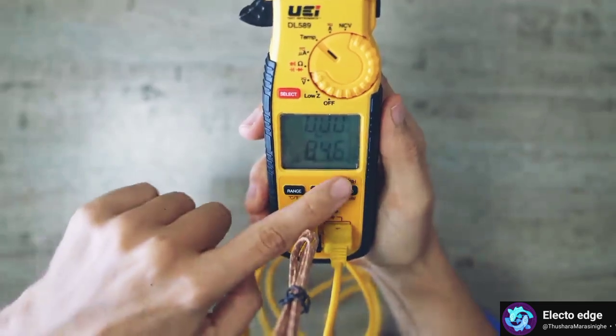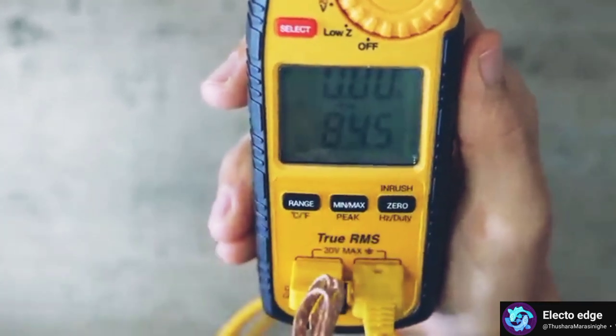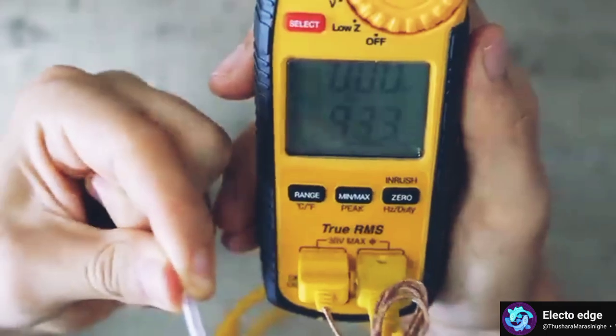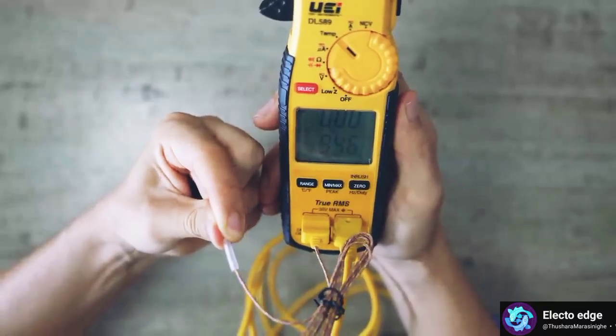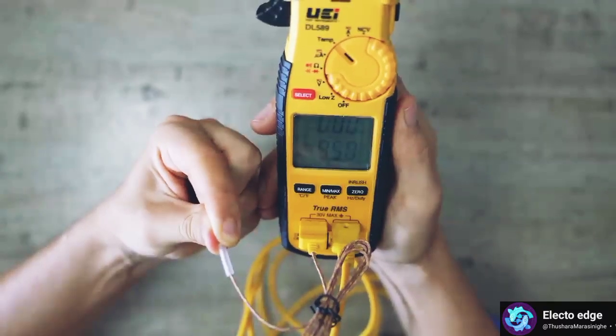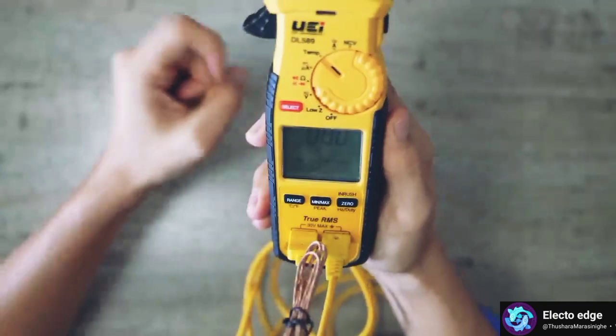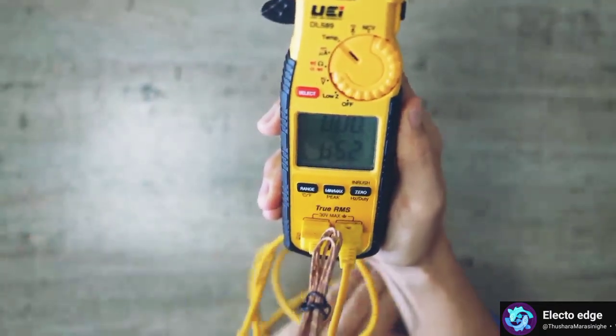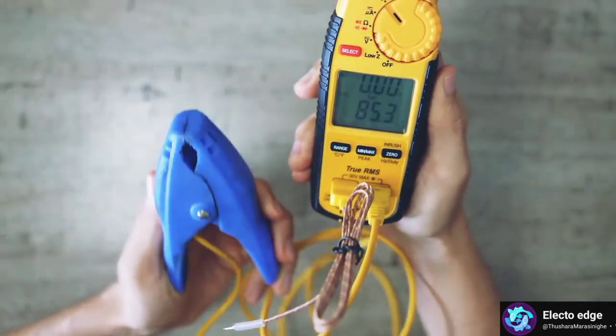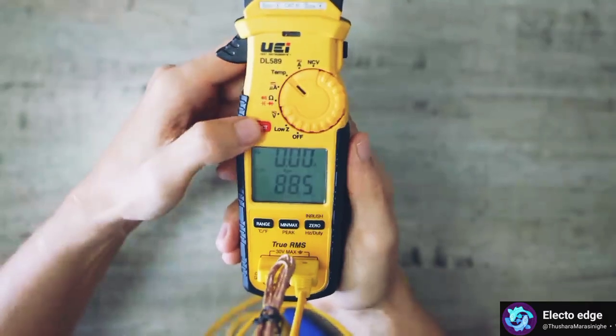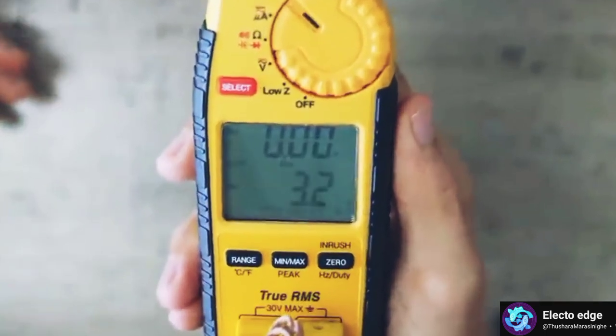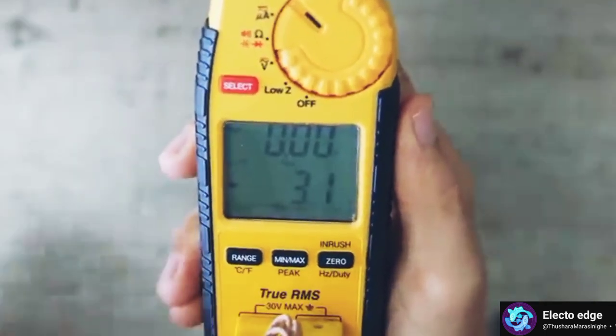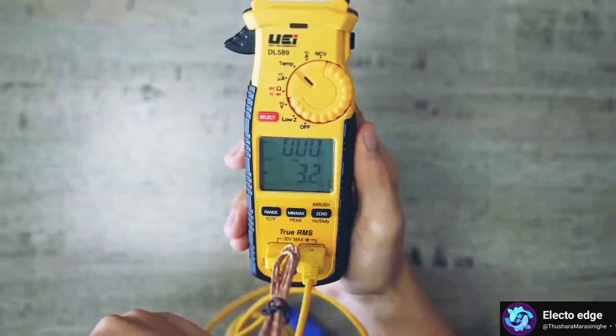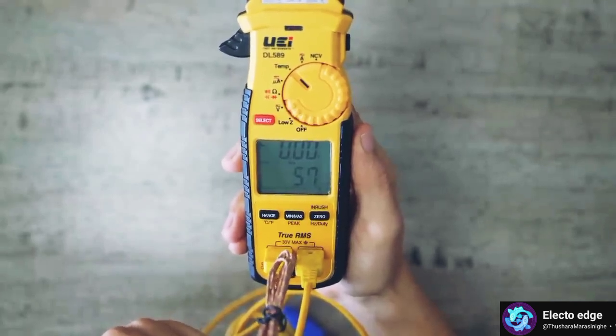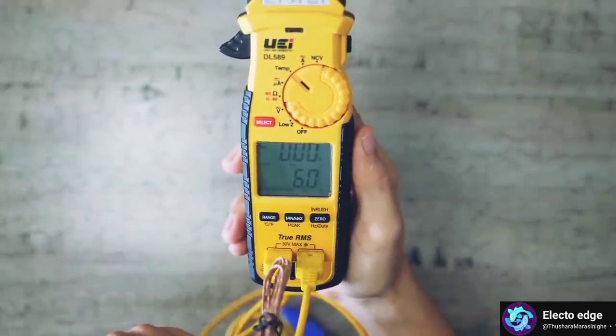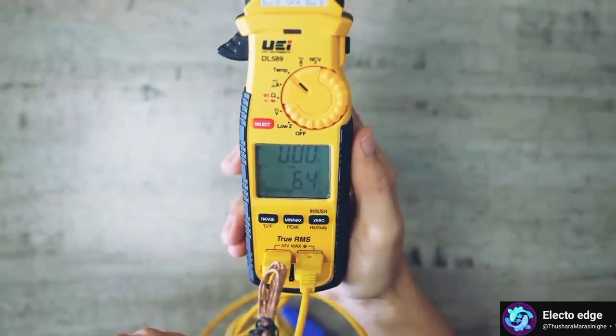So right now I have T1 selected, which is the first temperature probe, this guy right here. If I grab it with my fingers, you can see the temperature is climbing up. And if I press select, that brings me to T2, which is my clamp probe. And if I press select one more time, now we're getting the difference between the 2. So if I grab this guy one more time to heat it up a little bit, the temperature difference between the two probes is about 6 degrees.